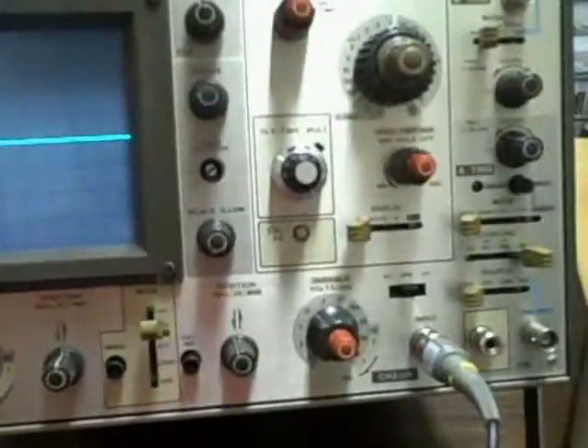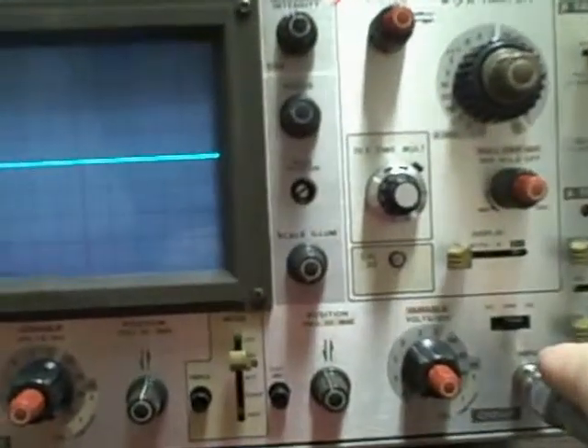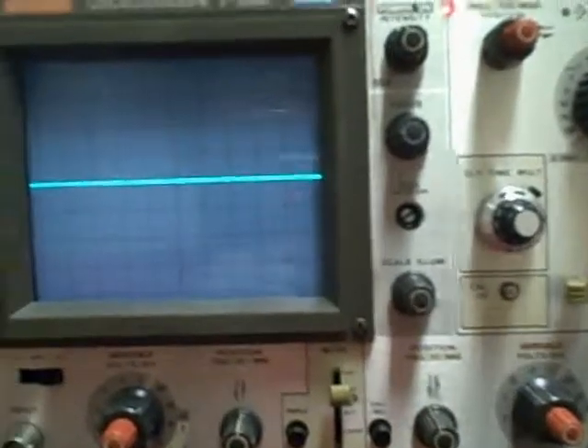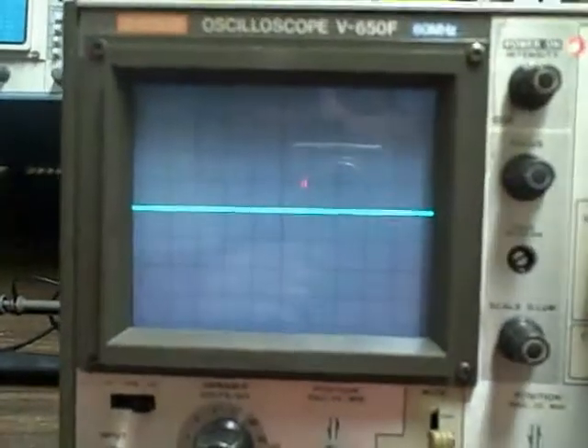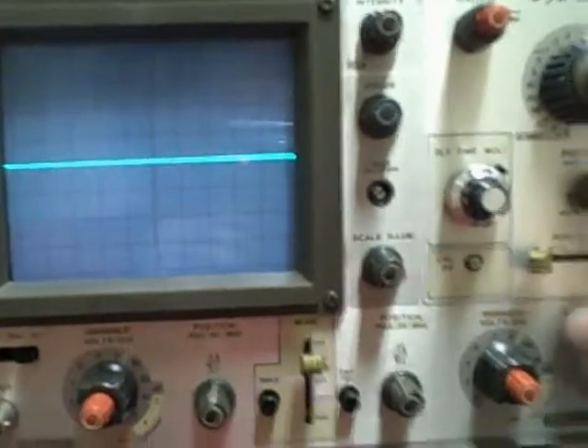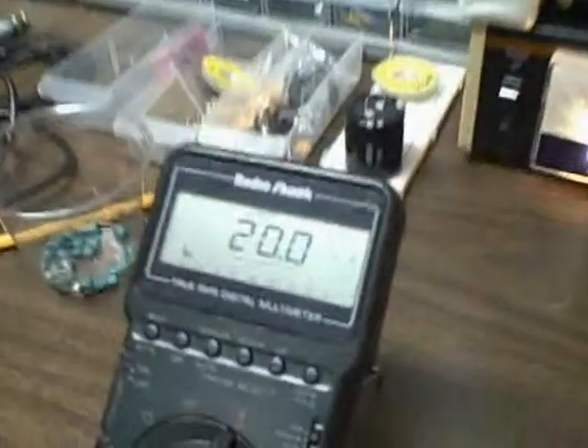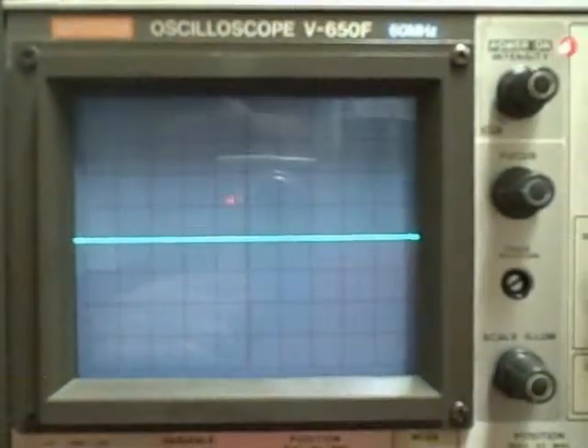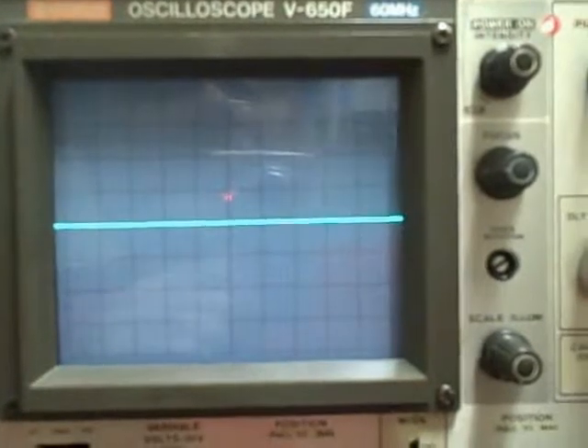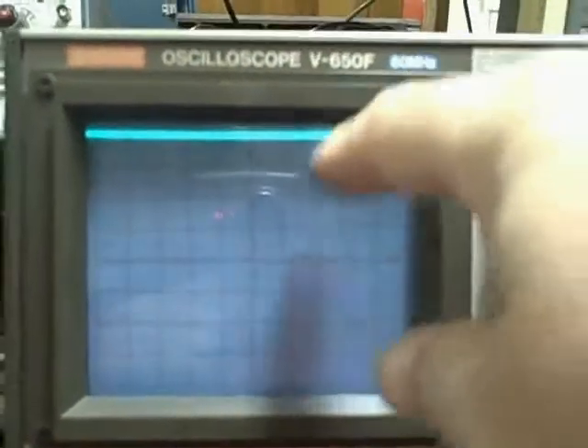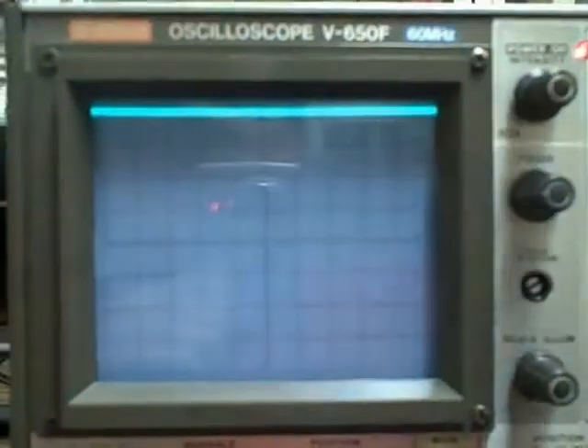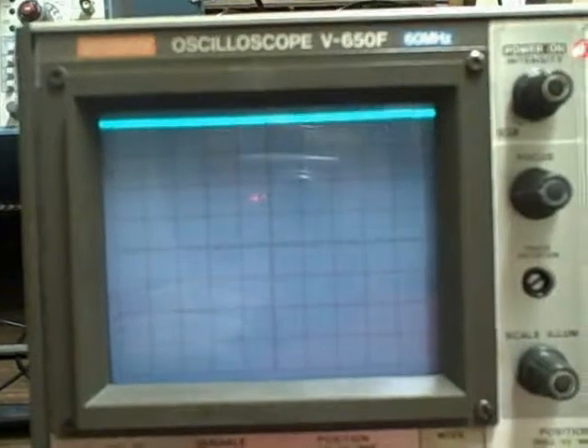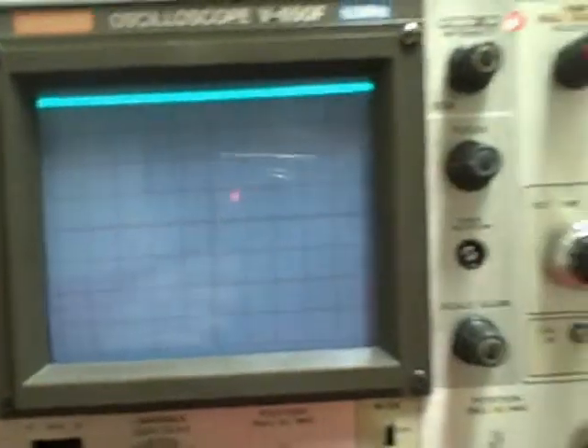Okay, we've moved ourselves to channel 2's input and we just zeroed ourselves. We have a 20 millivolt signal once again established on the lowest scale. We're running 5 millivolts per division, so when I kick this thing on I am reading full scale, 4 divisions up, 20 millivolts, which is where I want to be.